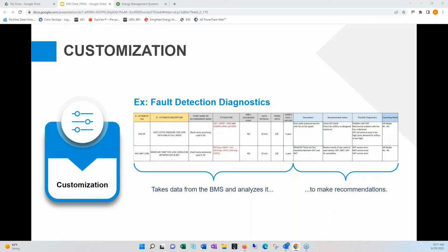It takes all these data points, the mixed air temperature sensor, outside air temperature sensor, and return air sensor, and performs an equation, shown there in red text. If that condition is met, it spits out a fault. But it's much more than just a fault or an alert.